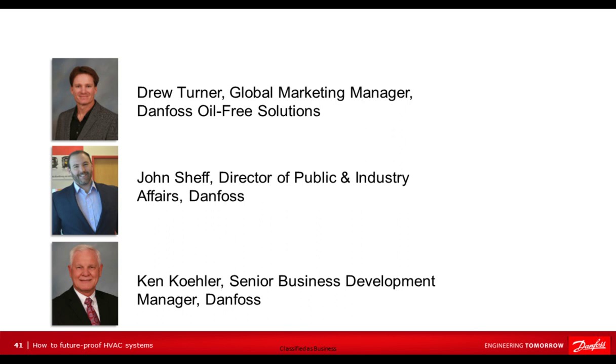I think for the specific solutions Danfoss has for that, Ken's probably the best to speak to it. But sure, I can touch on it first. So from our standpoint, what we generally see is that oil-free Turbocor-based systems are in general going to provide a less than 3, in some cases up to around 5-year, payback versus the alternative technologies you could utilize. If you incorporate the long-term performance and maintenance over time, it'll bring it even shorter than that, less than 3 years.